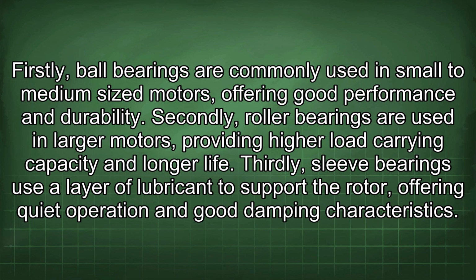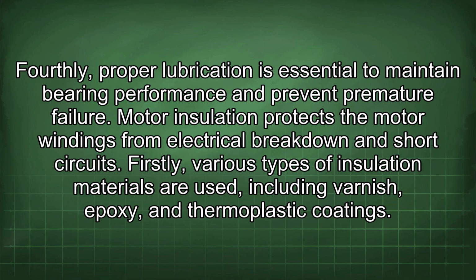Firstly, ball bearings are commonly used in small to medium-sized motors, offering good performance and durability. Secondly, roller bearings are used in larger motors, providing higher load carrying capacity and longer life. Thirdly, sleeve bearings use a layer of lubricant to support the rotor, offering quiet operation and good damping characteristics. Fourthly, proper lubrication is essential to maintain bearing performance and prevent premature failure.